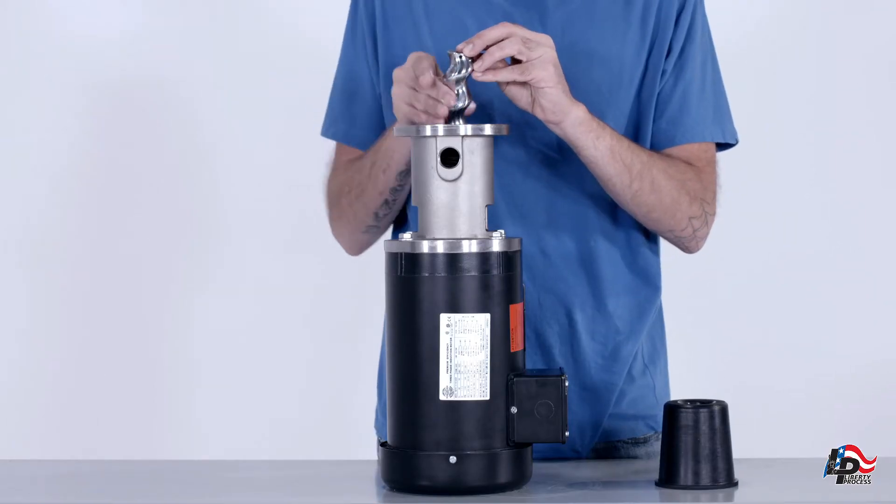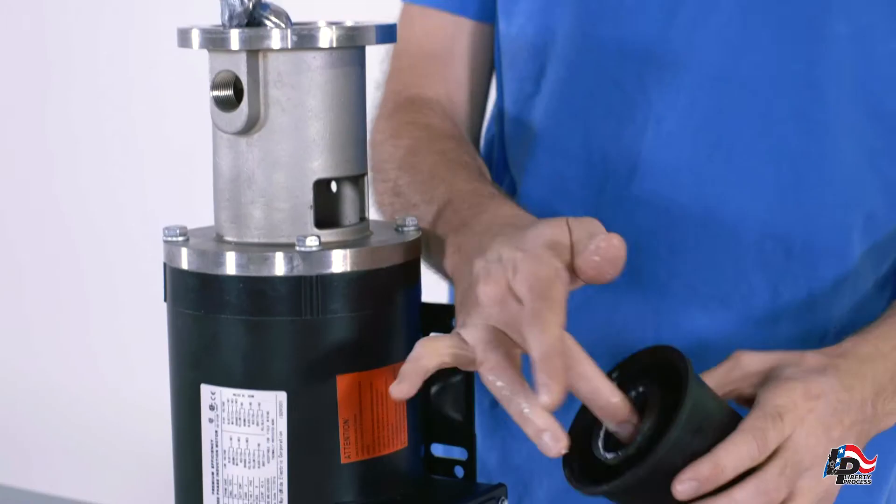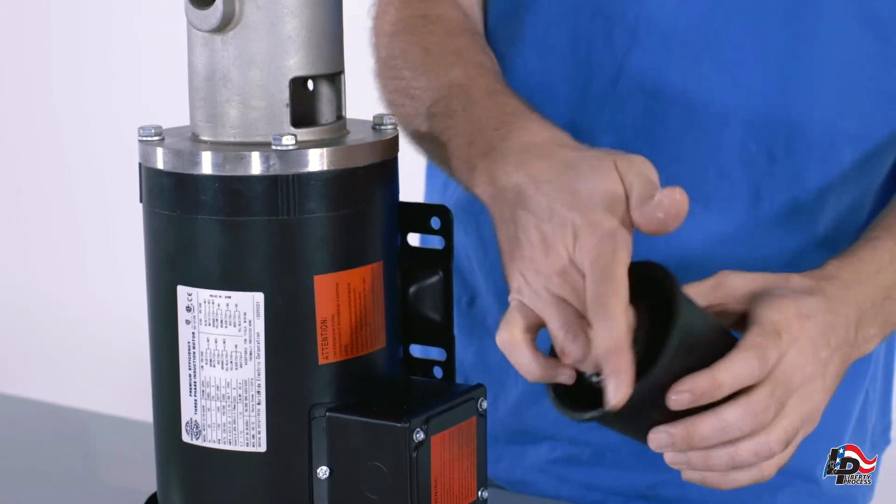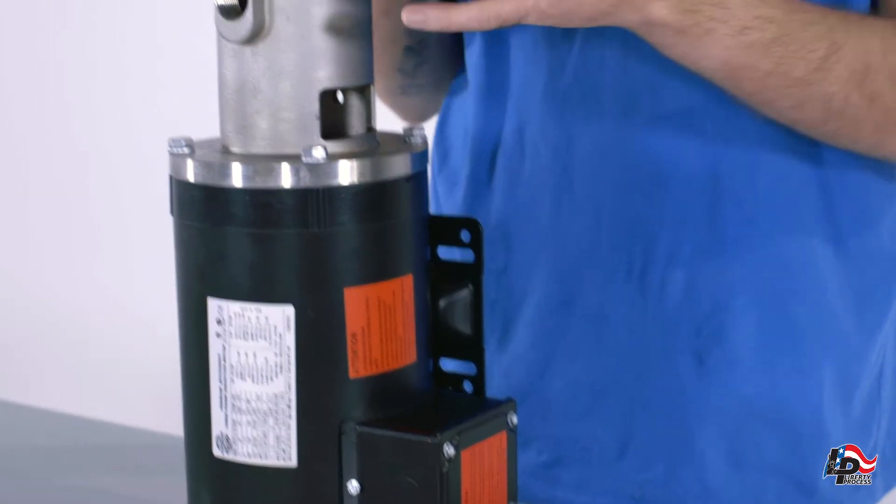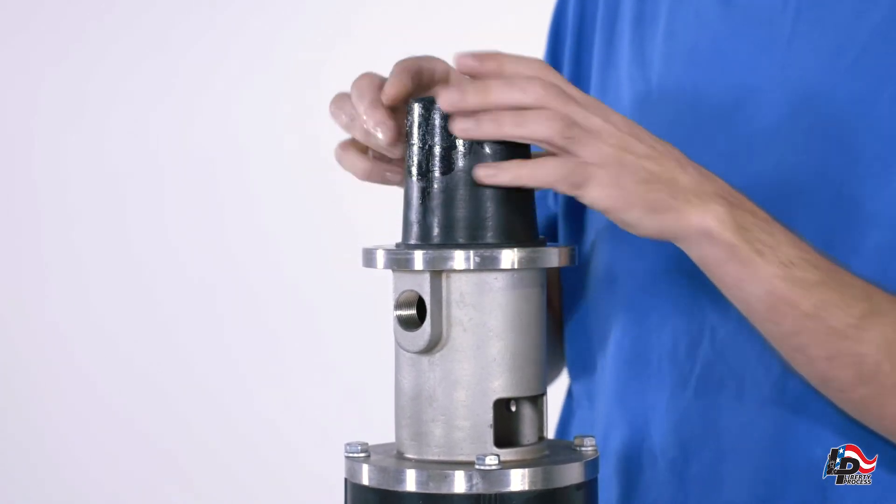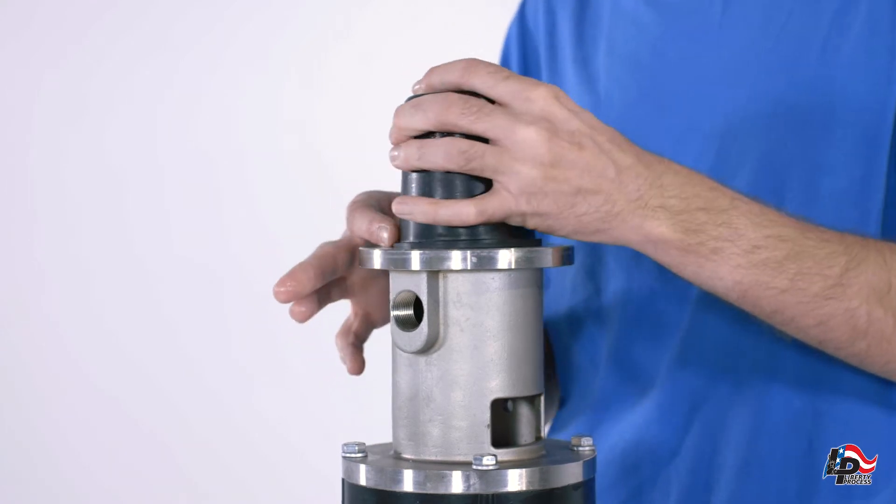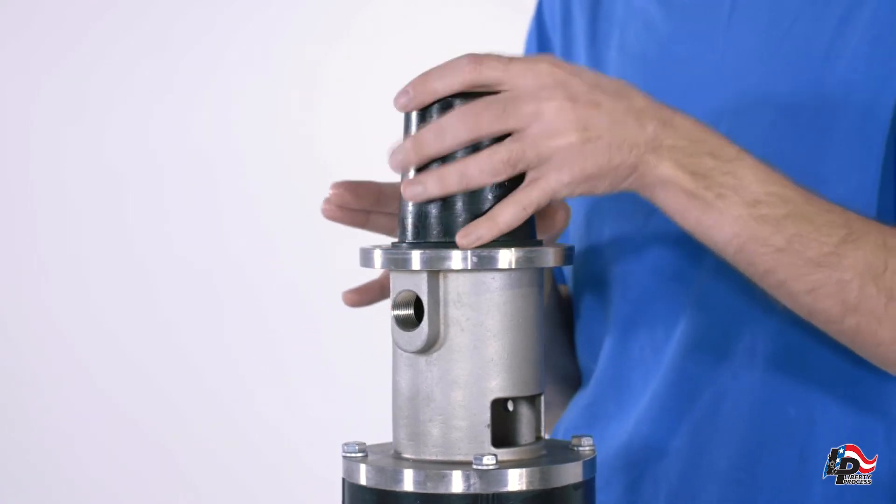Lubricate the rotor and interior of the stator with liquid hand soap. Slide the stator open side down onto the rotor and push down. The stator will seat itself into the channel on the discharge casing and acts as a seal.